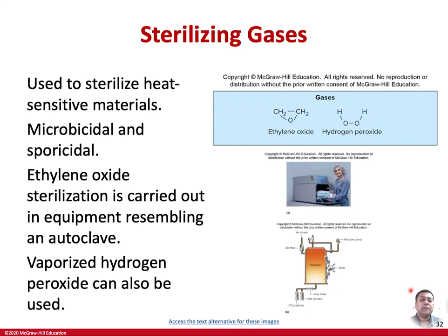On the other hand, the biological safety cabinets that we saw several pictures of can be decontaminated by using vaporized hydrogen peroxide. These are used at a wide variety of concentrations, between about 140 to 1400 parts per million, and that can disinfect or decontaminate, but not sterilize. It is pretty safe to use because the hydrogen peroxide is broken down into oxygen and non-toxic water.